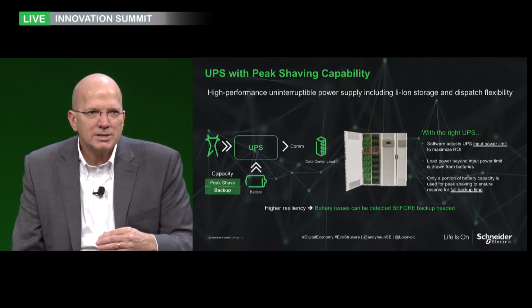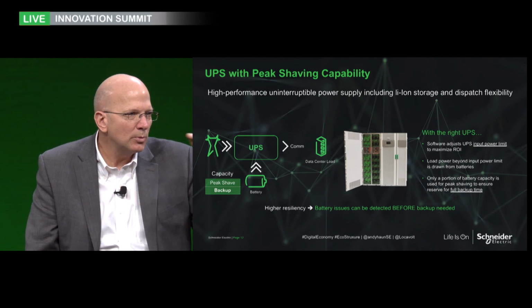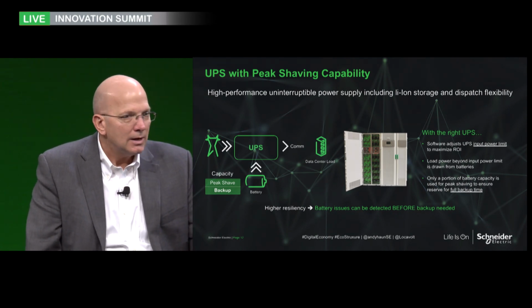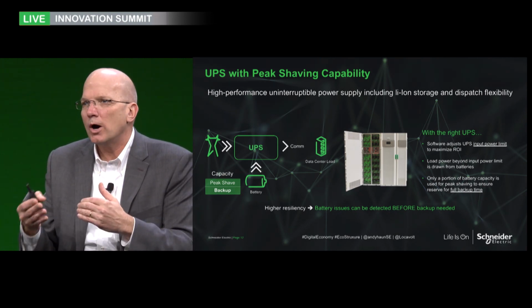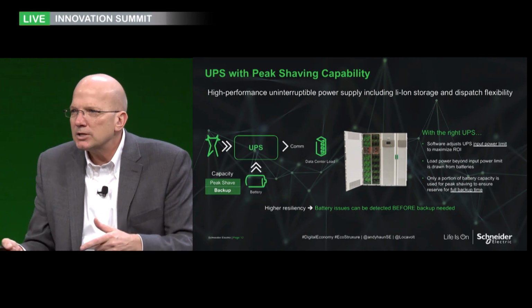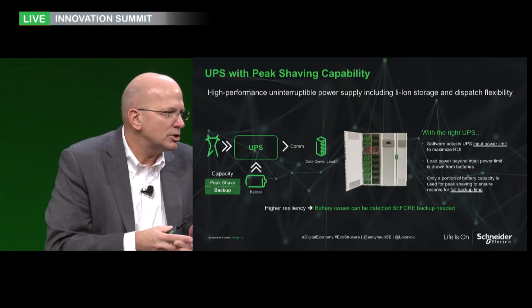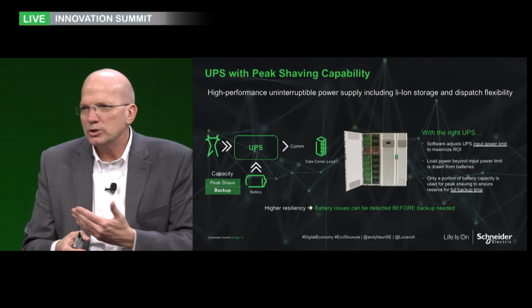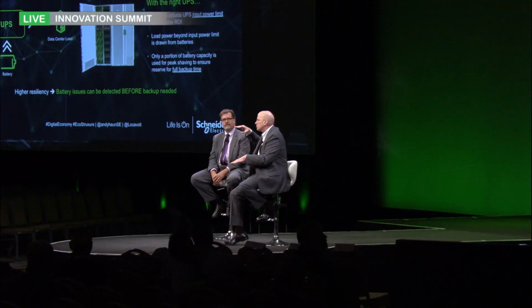We have controls in our UPS now that you can command that UPS to be a dispatchable asset, and that dispatchable energy load can take the load off of the utility, saving you energy cost when the cost of energy is highest. Or in the case where you have mixed in additional local generation assets and they're not available, such as intermittent generation from PV, and you don't want the loss of the PV to force you to go back up on the utility cost asset, you would then dispatch this UPS, and it would pick up the load until the PV came back online. This is an important tool for managing all of the energy in your data center power infrastructure. It's an adder, and it can directly replace a current UPS.